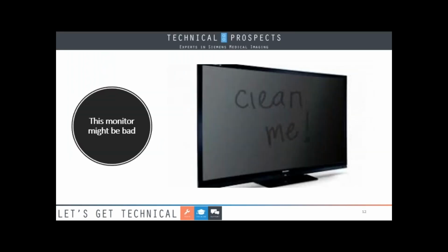Monitors are one of the easiest issues to troubleshoot. If the monitor has nothing on the screen, look for a small power on LED that'll be right about there. That'll tell you it has power. If you have any doubt, just measure it. It's just a regular socket going in. Some work off of 110, some are working off of 220. Doesn't matter, it's all the same. You can unplug it and just measure it.